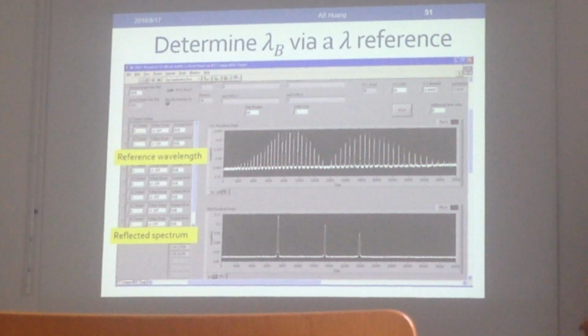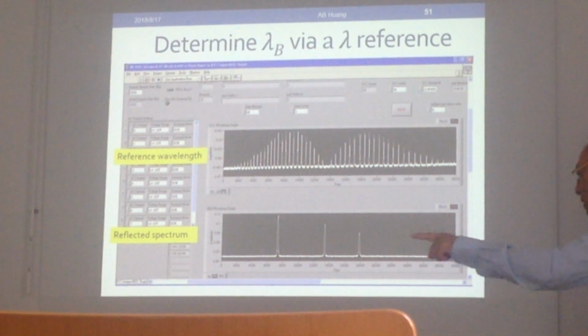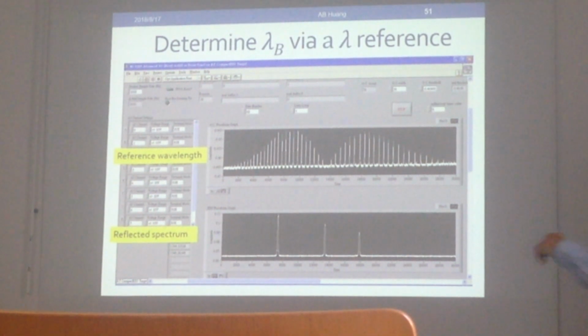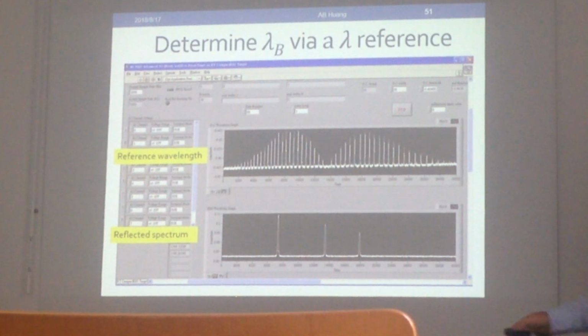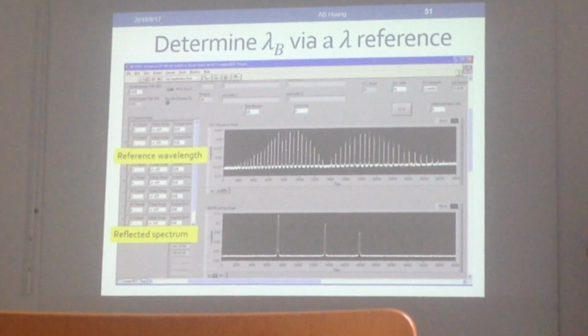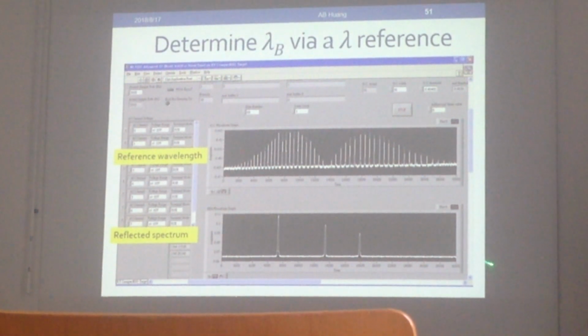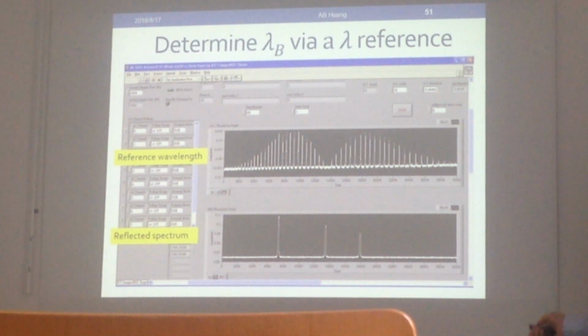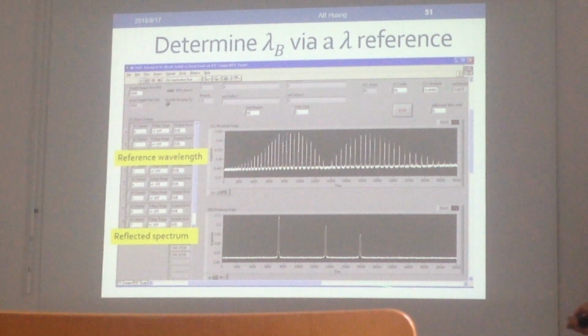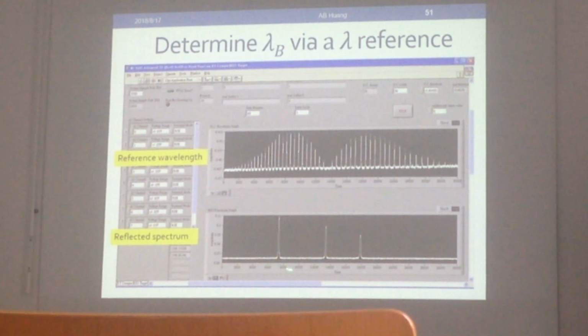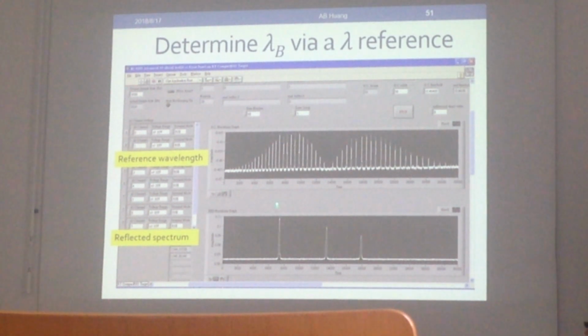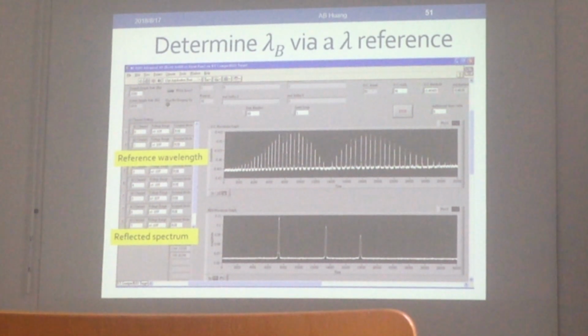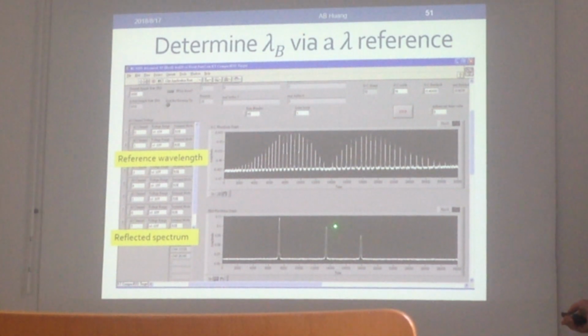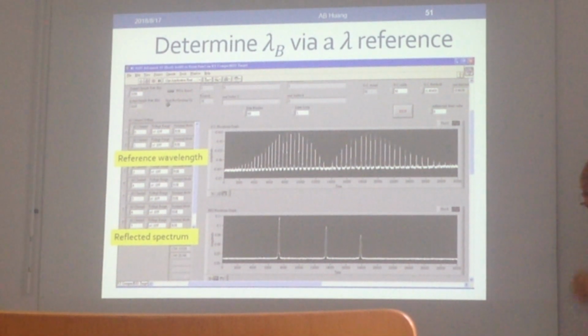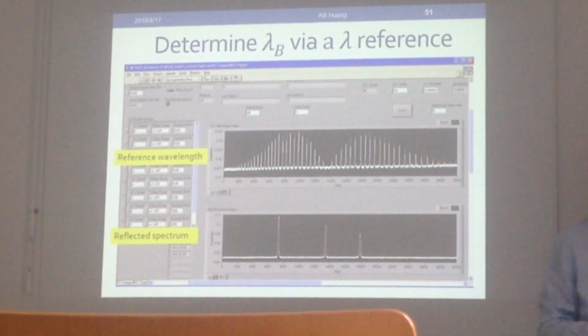This is the sequence. Every time we shoot the light, this is not like OTDR in pulse. This is continuous shooting. So when I start taking readings, every time I start scanning the reflected light wave, usually it's about 30 to 50,000 data points. In other words, this is only the sequence of the data points that I received back from the optical fiber. The first peak occurred, let's say here, and then 4,000, 6,000, this is 8,000. Let's say this is 7,500. So what is that wavelength? The 7,500 is only the sequence number, and then the next one is, let's say, 13,500, and so forth. So what does that sequence correspond to in terms of wavelength?